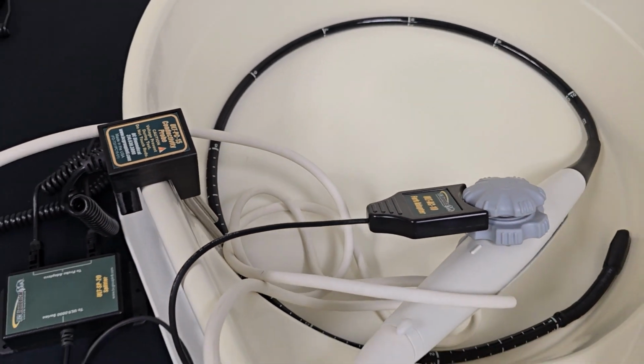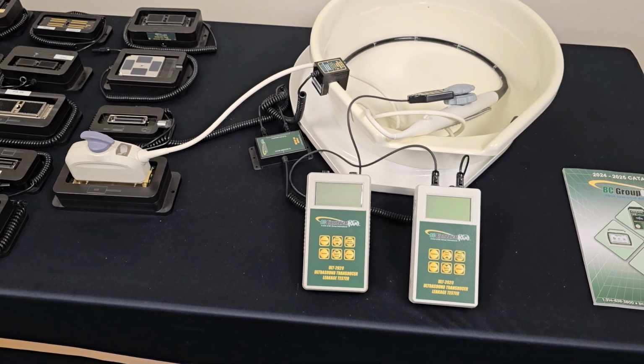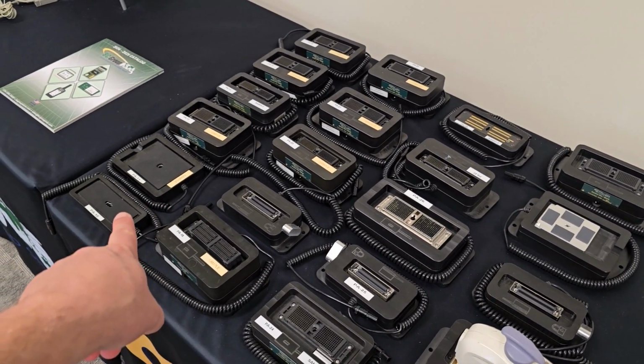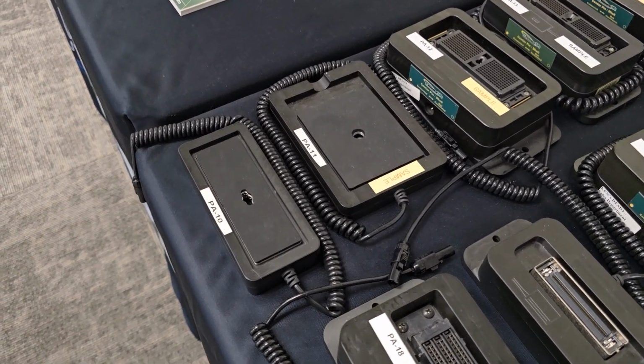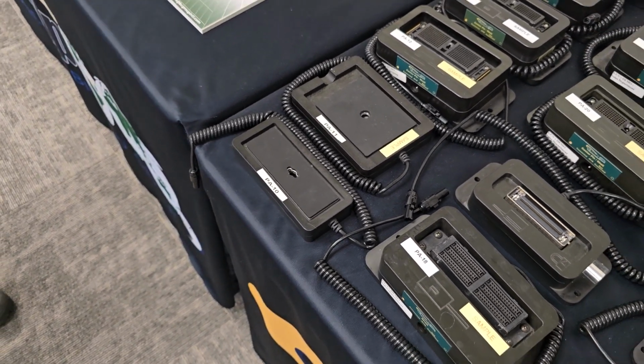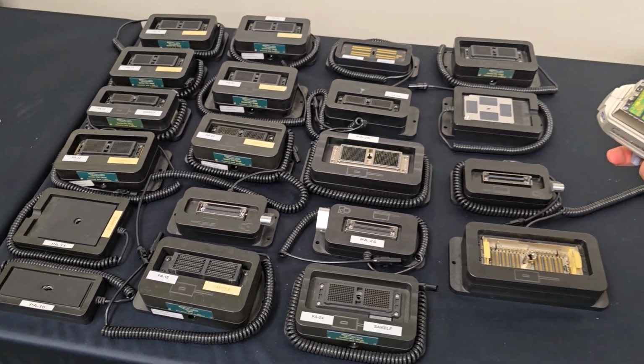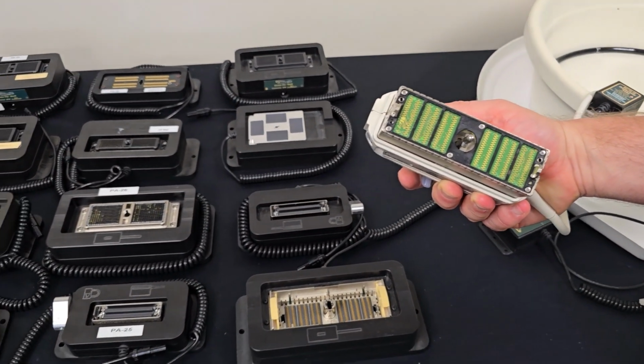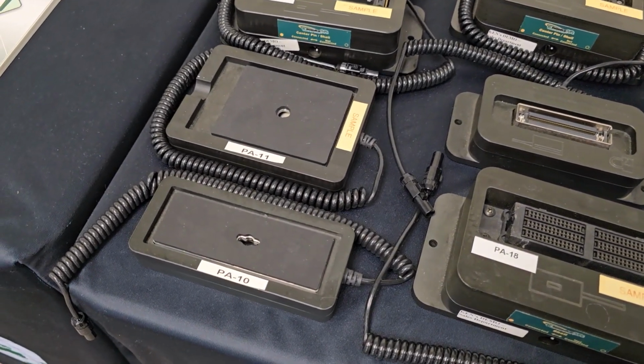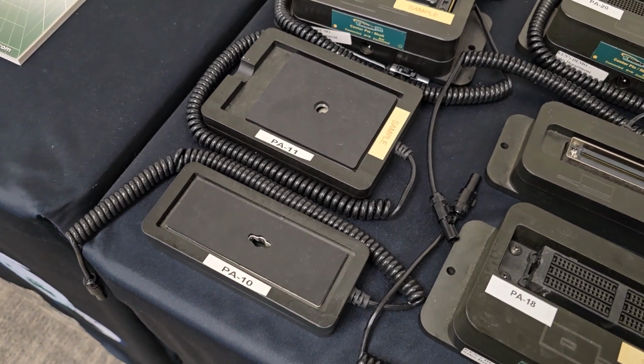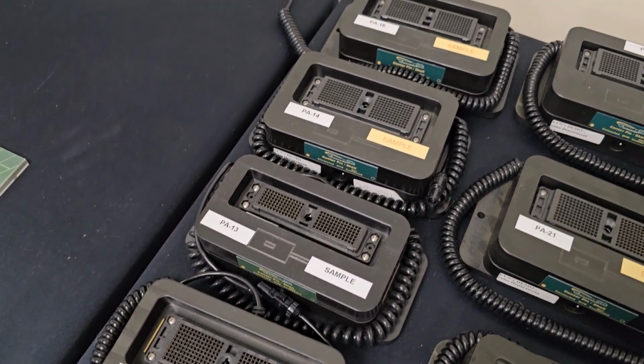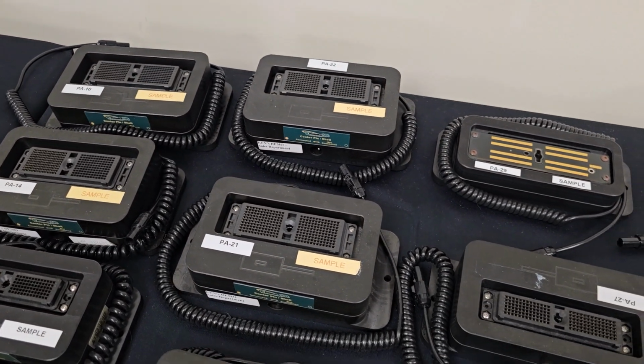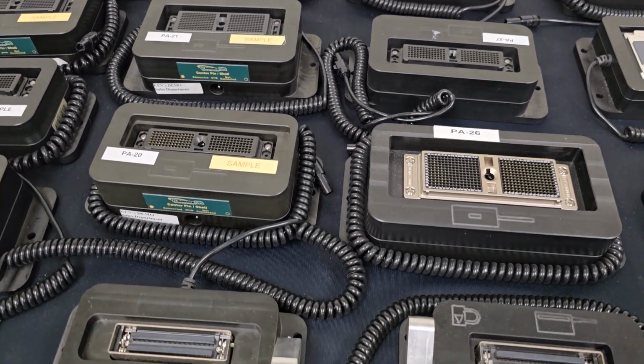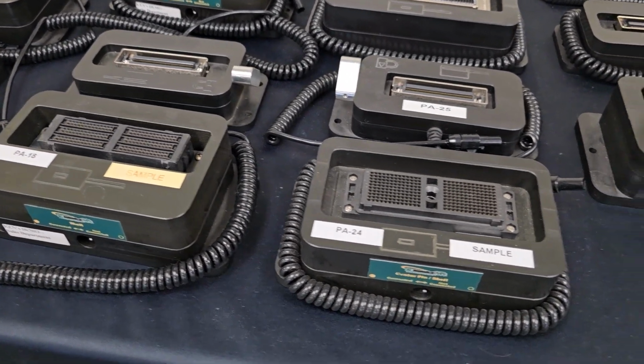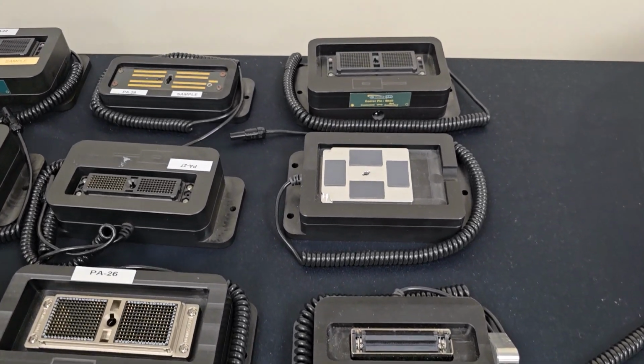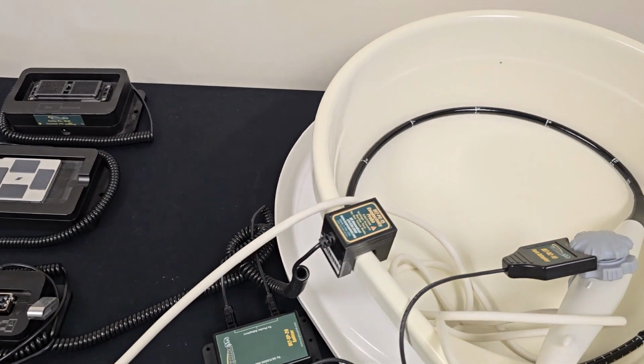And what we found was that initially there was one adapter. This one adapter fits all was the initial mentality. And that's the conductive rubber pad. And so you can imagine, if you have a connector on your ultrasound probe that looks like this, well, that's not necessarily going to be compatible with that rubber pad. Right, because they're all going to be at different heights and widths and thicknesses. Exactly. So what we decided was, the manufacturer already has a connector picked out for their ultrasound machine. So why don't we use that connector in our design and make our adapters using that same connector? So this way we get the exact same connector that the OEM is using. Interesting. So now it leads to a lot of adapters.